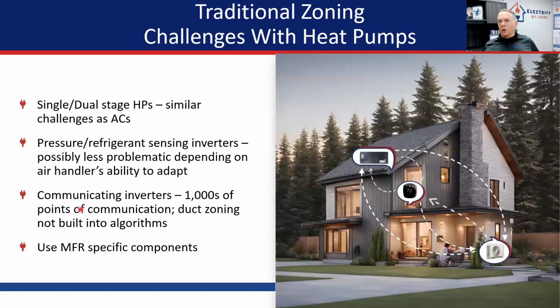Okay. So the challenges with heat pump systems, and we talked about this a second ago, but single and dual stage heat pumps have similar challenges to AC units. If you have a dual stage heat pump and you set it up on a zoning system, it's going to be better than if you put it on a single stage or some inverter systems, because inverter systems are not designed to do this.